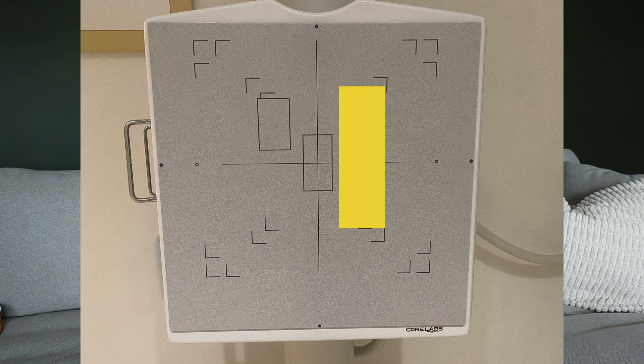Another factor that can affect AEC is proper positioning of the patient. If the part of the patient is not aligned with the selected photo cell, you're not telling that photo cell when the appropriate time is to shut off the exposure. For example, if you're doing a c-spine x-ray and the patient's spine is not aligned in front of the center cell on the bucky, that cell is going to receive too much radiation too quickly and will terminate the exposure, resulting in an underexposed image.